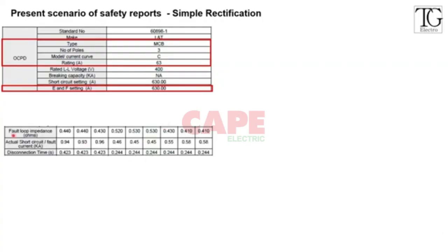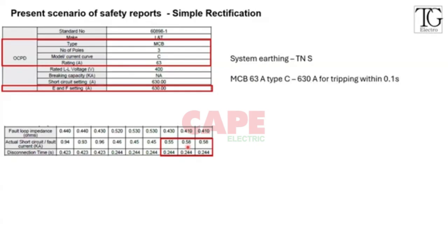So in the site scenario the actual disconnecting time is 0.2, and the actual short circuit fault current is going to be around 0.5 kA, 500 amps. Now, take this fault scenario as an example, and let's keep the earthing system as TN-S. For an MCB of 63 amps, C type, to trip within 0.1 seconds, you need something around 630 amps of current. But here we are getting only 500 or 550 amps, so we need 630 amps of current.